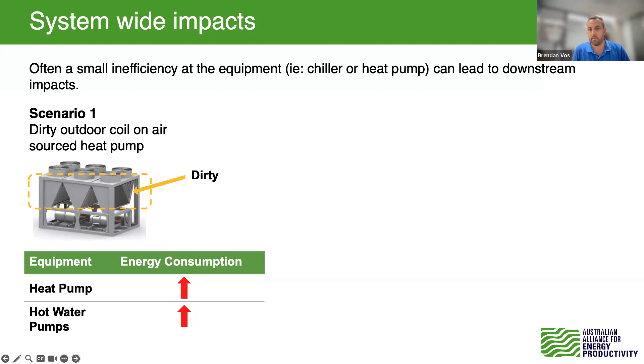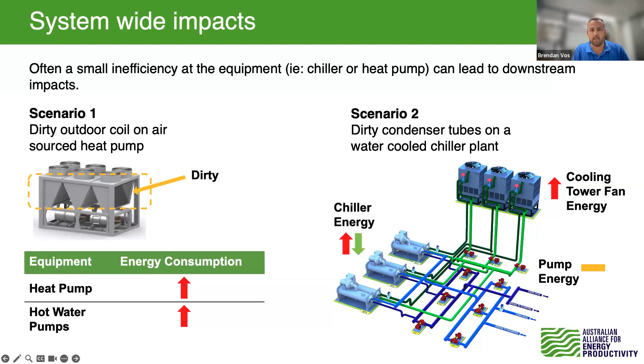So what might happen here is my fan energy will certainly go up because the control system will try to ramp to meet my previous set point, but my chiller energy could stay static because my cooling towers just run a bit harder, and I might never realize that's happening. My pump energy will be flat. So the anomaly is the fan energy increasing, and Brad's example before - that sort of data would definitely find this very, very quickly.